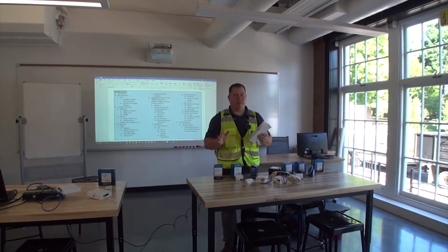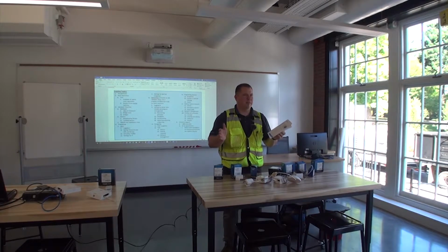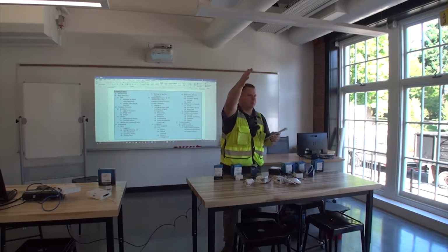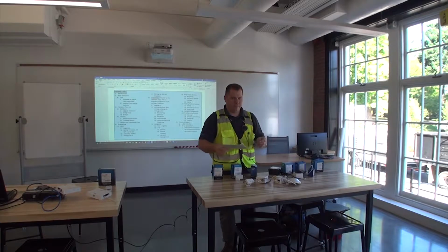My general rule of thumb is no more than 9 or 10 devices between power packs, and that's a substantial number. Most of your rooms aren't going to have that many. The only rooms that go beyond that are common spaces, hallways, or cases where you've connected multiple rooms together.